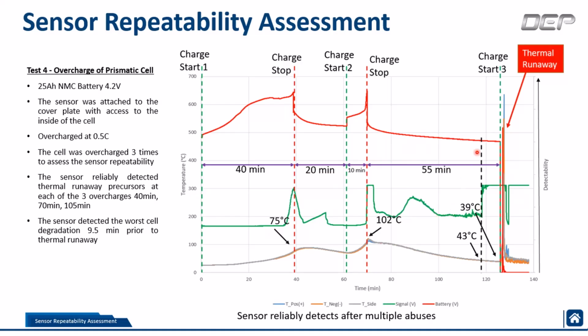And even when the voltage was at its lowest point here, even before we started the overcharge test, and the thermocouples reached around 43 degrees, our sensor detected a huge jump in the electrochemical changes, pretty much telling us that thermal runaway is imminent. This is going to happen.